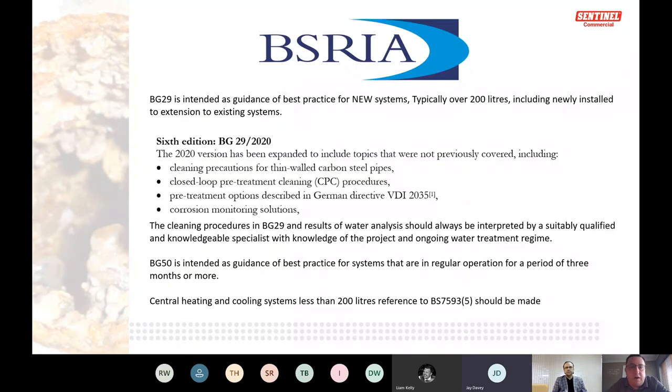The reason we wanted to cover corrosion now is the new BG29, one of the guiding documents for how you should look after a commercial system — anything over 200 litres. The sixth edition was recently launched earlier this year. It includes cleaning precautions for thin-wall carbon steel pipes, closed loop pre-treatment cleaning, and some information on VDI 2035.